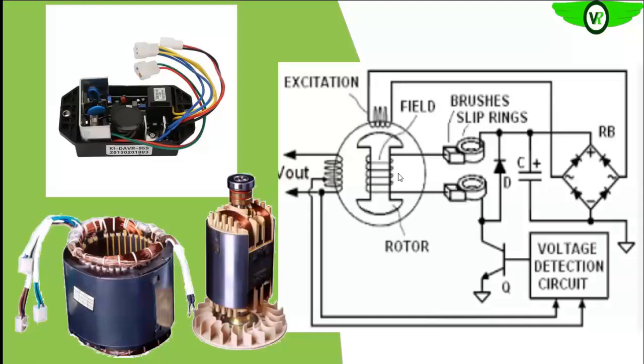So if you also look, you see another wire that is sent from the excitation winding to the phases of the diode assembly in the AVR. Okay, so these wires that are represented here, they are sent to the phases of the diode assembly in the AVR. So this excitation winding, what it does is that it's wound on top of the main armature winding. What it does is that it produces the excitation voltage, okay?